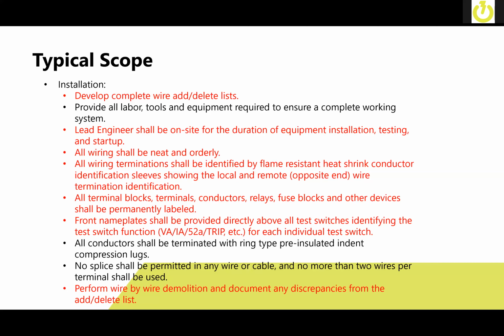Terminal blocks, terminals, conductors, relays, fuse blocks, and other devices are permanently labeled, be that with a phenolic tag that's sticky back. They do stick on. You can use some silicone to keep it on there if you like, or sometimes customers like them to be applied with set screws.